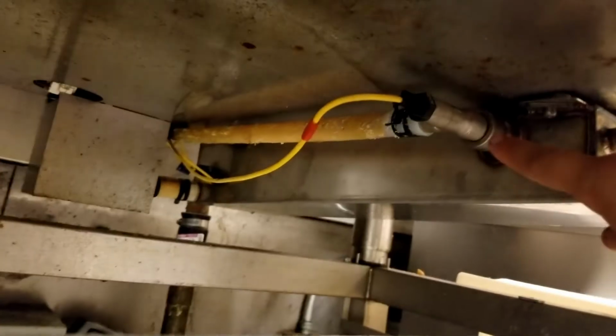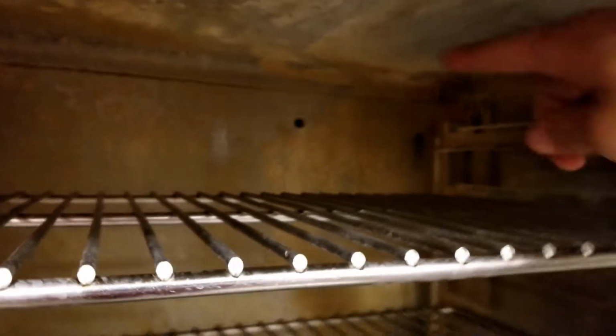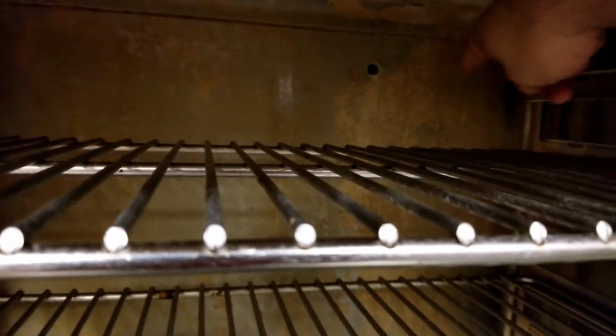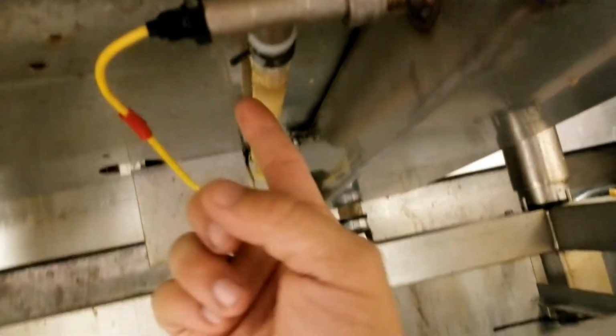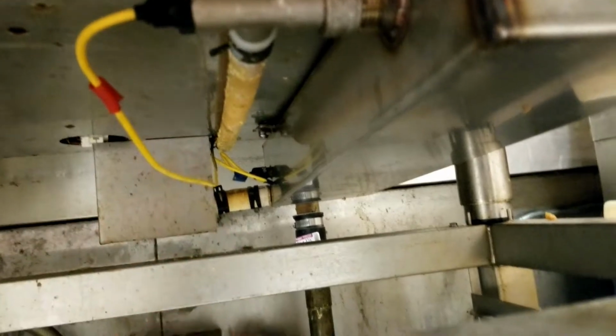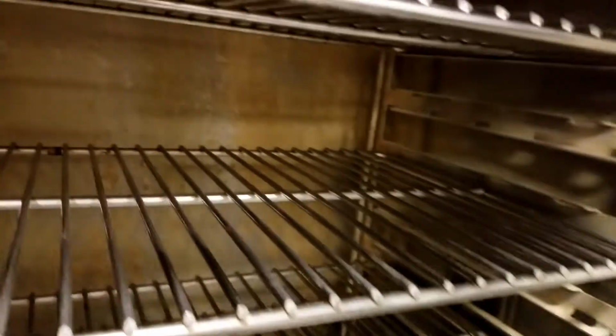Or B, your B5 probe, which is this one right here that goes to the front to this little T-fitting, is not sensing the steam. So what you need to do is go in here and make sure that hole back there is cleared out, because the steam will go through it, down a hose, down an elbow, through this hose here, and it'll touch this probe, and that's how it tells there's steam.